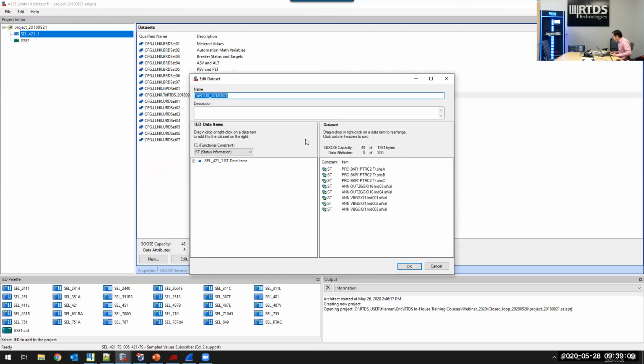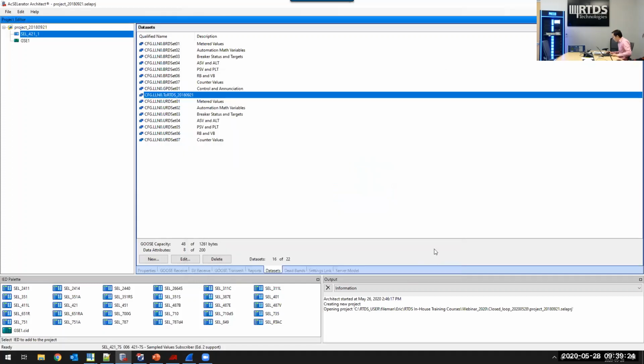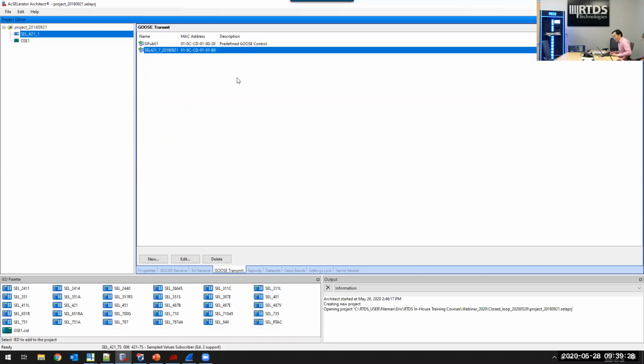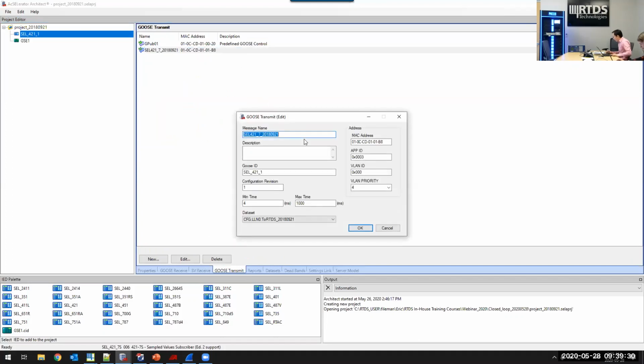An output data set named TWRT, which contains the required control signals, was created. For example, you can see the trip signals here, and there's a reclose, and there's a permissive trip as well. Then a Goose control block and associated communication parameters are created in this Goose transmit tab.